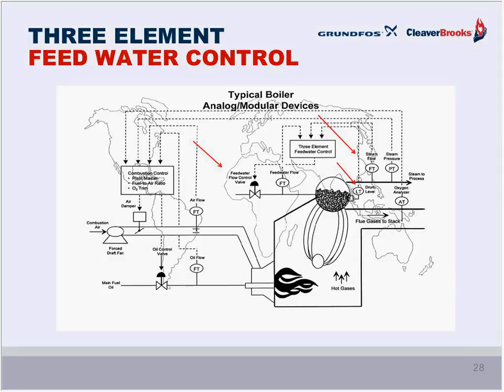This is an anticipatory control or feed-forward control, which sends a signal to the feed water regulation valve if a sudden drop or increase in pressure or flow is sensed, indicating a process load increase or drop, and thereby adjusting the flow of the feed water, even if the drum level is within expected tolerance. So it's an anticipatory control strategy.